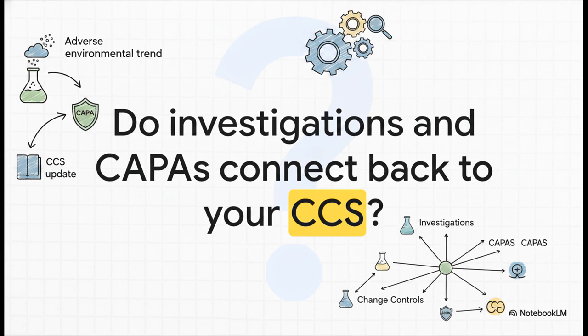A facility that inspects well is one that truly knows its data. It can tell a coherent, interconnected story. If you've got an adverse environmental trend, the inspector wants to see that it triggered a CAPA, and that CAPA ultimately resulted in a meaningful update to your contamination control strategy.